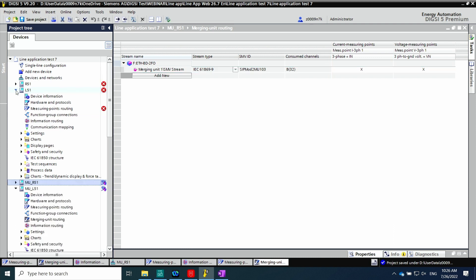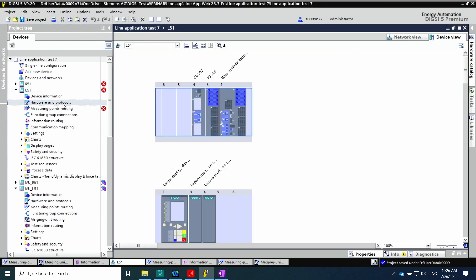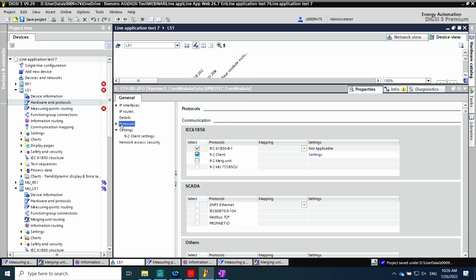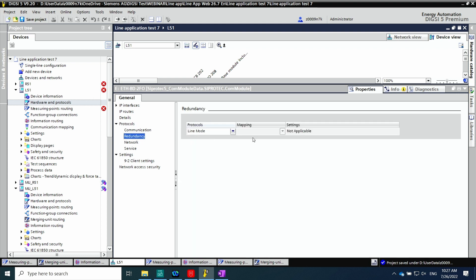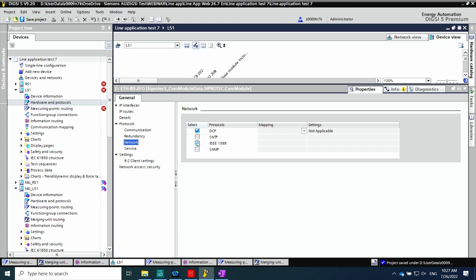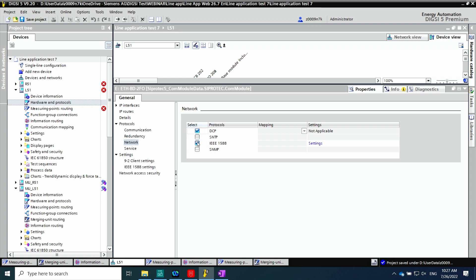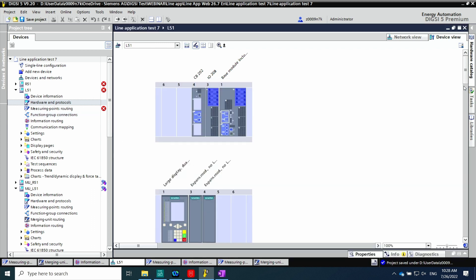Now let us configure the client LS1, which receives information from the low power instrument transformer. In hardware and protocols, the IEC 61850-9-2 client is selected to receive the sample values from the merging unit. Redundancy communication can also be configured as mentioned above. After that, the IEEE 1588 protocol is selected. In this application there are two communication cards: one card for the process bus to collect analog values from the conventional instrument transformer or low power instrument transformer.